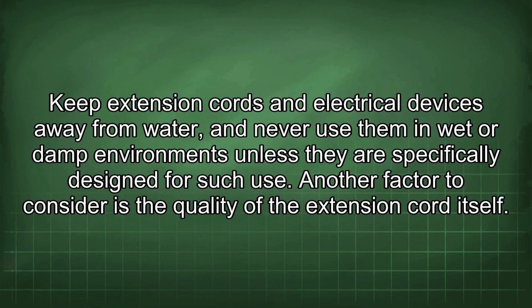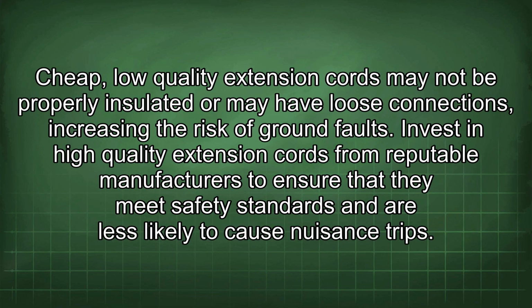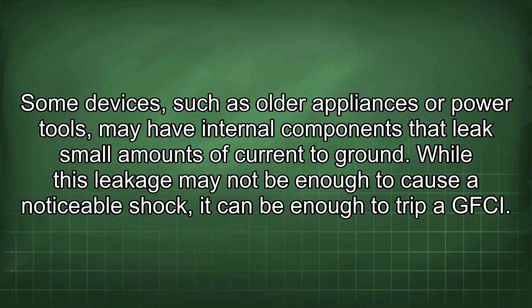Another factor to consider is the quality of the extension cord itself. Cheap, low-quality extension cords may not be properly insulated or may have loose connections, increasing the risk of ground faults. Invest in high-quality extension cords from reputable manufacturers to ensure that they meet safety standards and are less likely to cause nuisance trips. Some devices, such as older appliances or power tools, may have internal components that leak small amounts of current to ground.